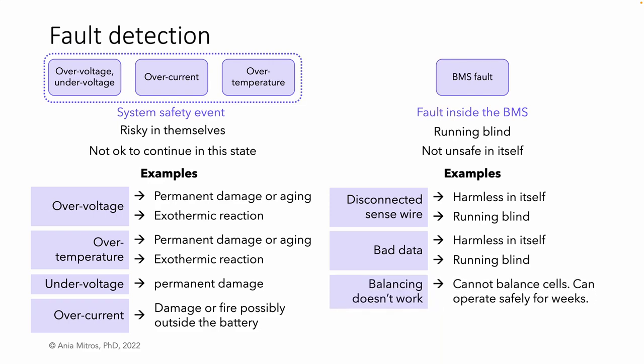A third example of a BMS fault is a problem with balancing. You could imagine a bad solder joint causing a balancing resistor to disconnect, with the balancing circuit no longer connected to the cells. The battery can continue to operate with this fault for a long time, weeks or months. Imbalance in itself is not a safety issue. If one cell is at top of charge at 4.2 volts, while another is at 4 volts, we're sadly missing out on using the full capacity of those cells, but there's no safety concern.